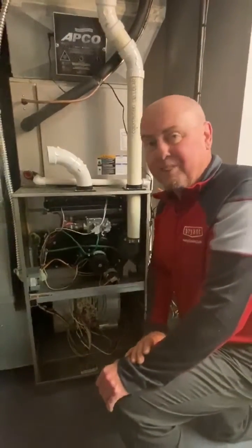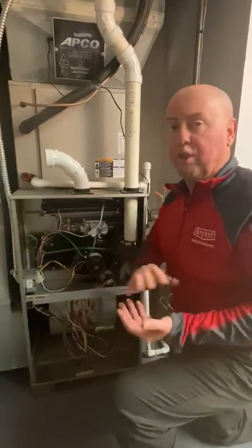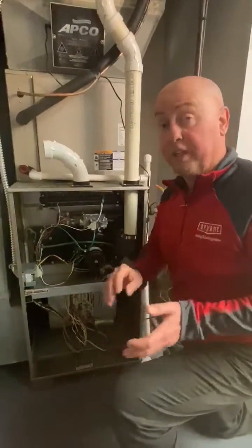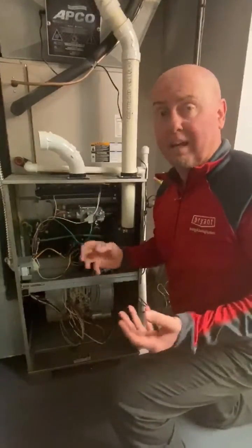Today I'm going to show you how easy it is to inspect a secondary heat exchanger in a Bryant furnace. Our secondary heat exchangers are fin tube. They will get dirty — full of dirt — and it will cause the furnace to overheat and shut down.